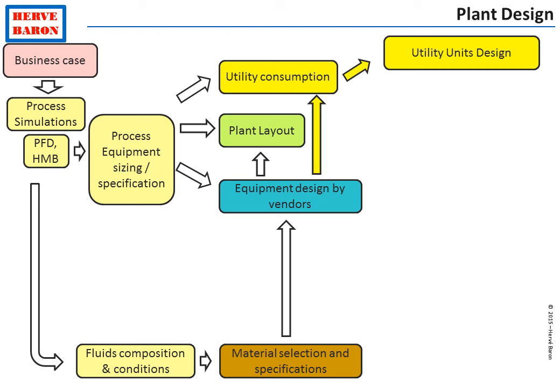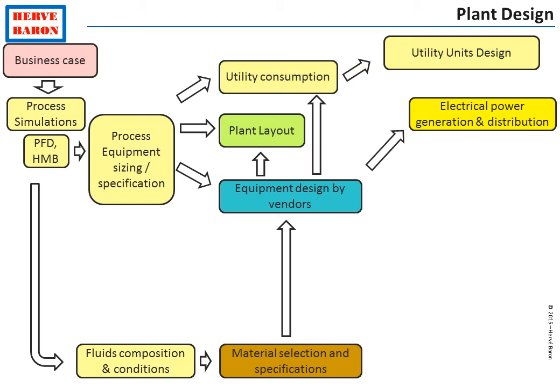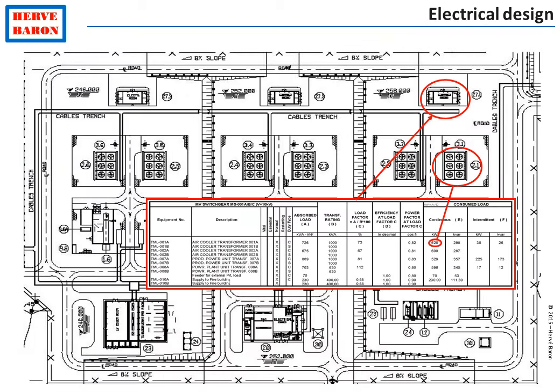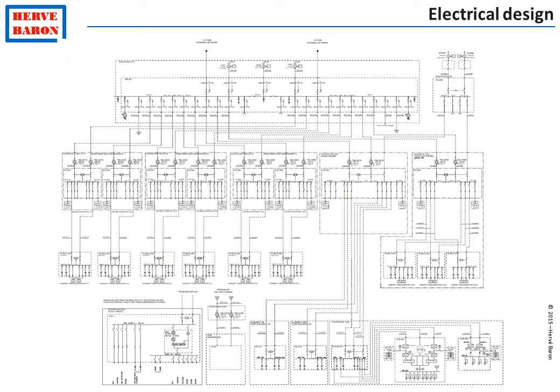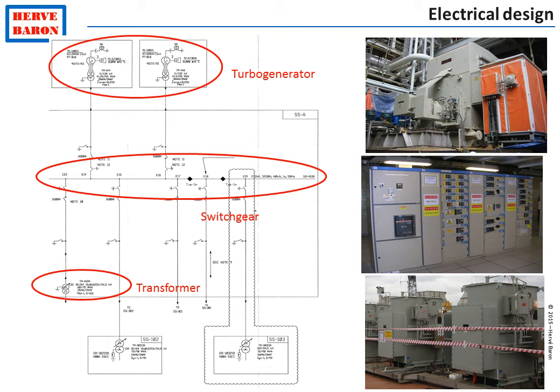Information from equipment vendors is not only required to perform the plant layout, but also to design the utilities. The utilities of the plant have to supply the required amounts of cooling water, fuel gas, steam, and so forth to the equipment. In addition, equipment vendors will advise the power consumption of their equipment, which will allow sizing of the electrical power generation and distribution — including defining the architecture of the electrical distribution as shown on the single line diagram — and sizing all distributed equipment such as transformers, switchgear, and cables.